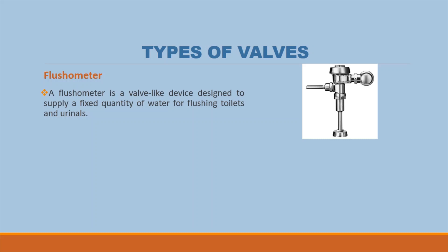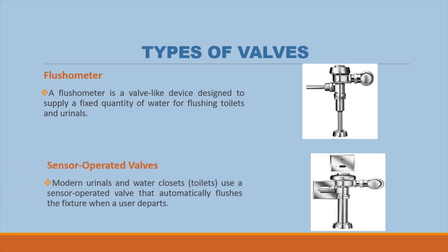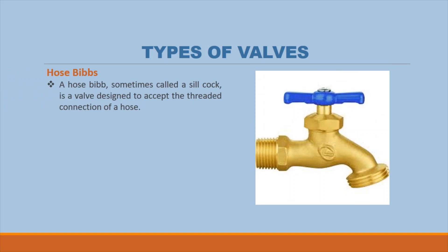A pressure reducing valve is an adjustable valve designed to reduce pressure to a specific setting. A flushometer is a valve-like device designed to supply a fixed quantity of water for flushing toilets and urinals; it automatically shuts off after a measured amount of water flow to conserve water. Modern urinals and water closets use a sensor-operated valve that automatically flushes the fixture when a user departs. A hose bib, sometimes called a sill cock, is a valve designed to accept the threaded connection of a hose, allowing water near the exterior wall to drain when the valve is closed to avoid freezing in severe winter temperatures.